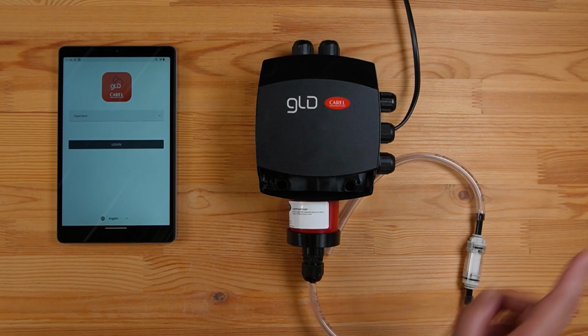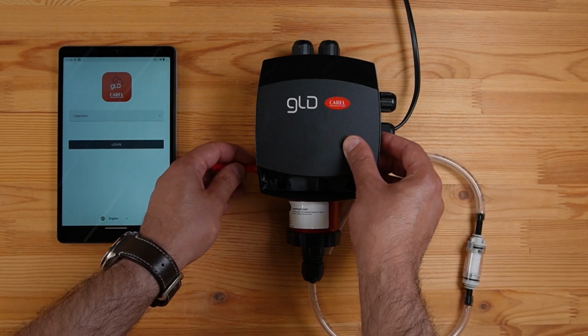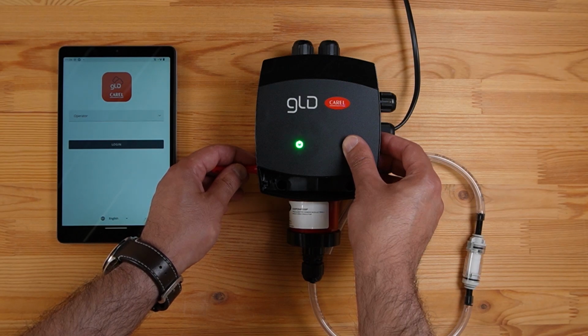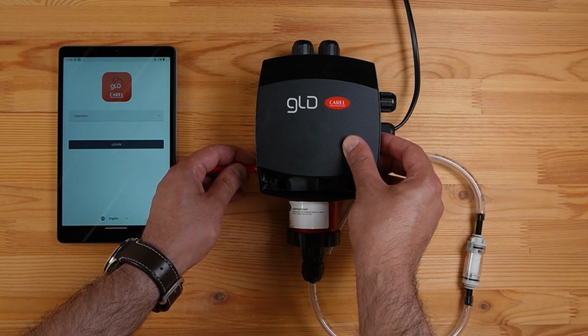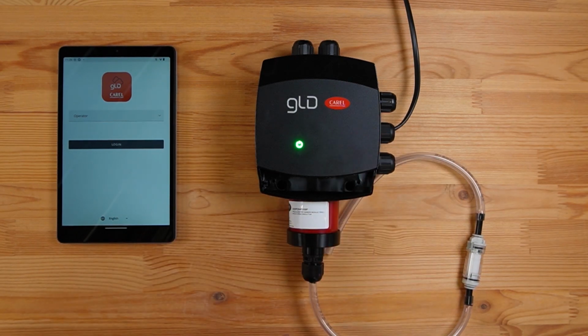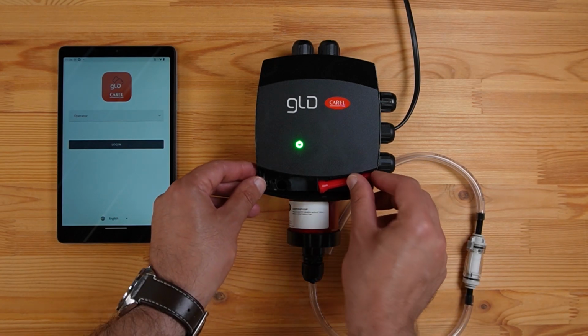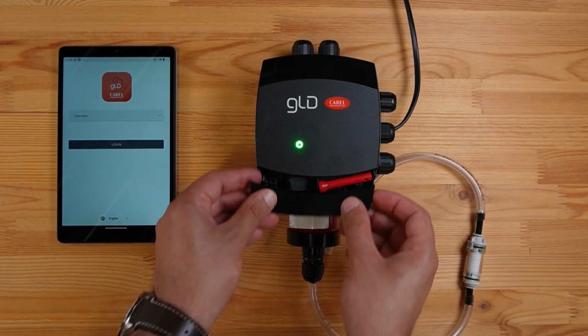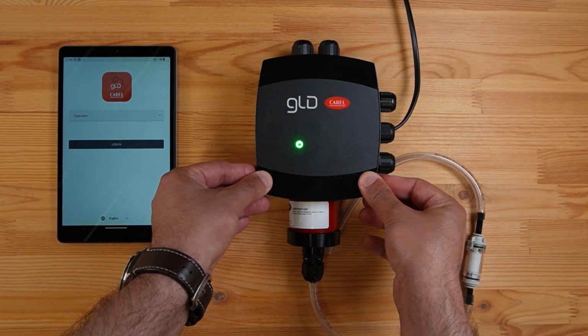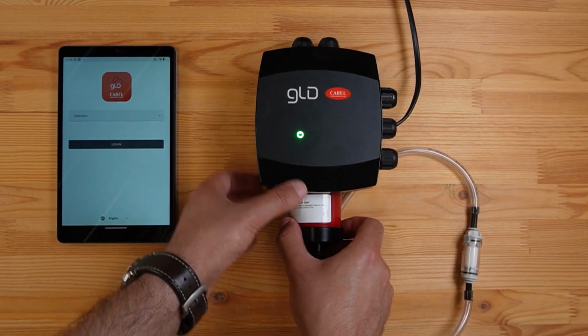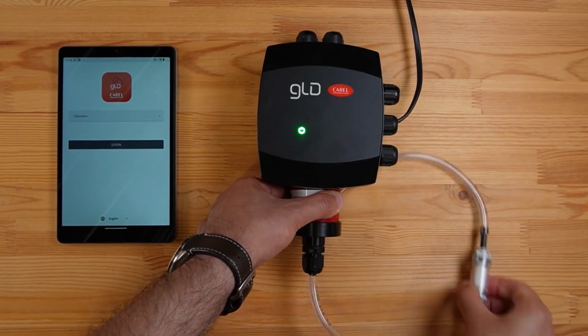This is done by holding the magnetic wand on the marked spot on the left side of the unit for 5 seconds. When the green LED light is turned on and not flashing any longer, the unit is in operating mode. Now unscrew the calibration kit from the sensor head.